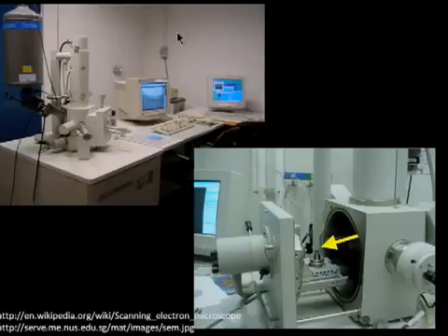And here's a picture of a typical scanning electron microscope, an SEM. So up here, we have the electron emitter, and this is the column with the optics and the scanning coils. And your sample typically sits in this chamber, and you can see it's on this little post here. And this is big and husky because it operates in vacuum. You couldn't get such accuracy with an electron beam if you had it in air, because air would scatter the electrons. So there is a constraint of the technique in that your sample has to be vacuum compatible.